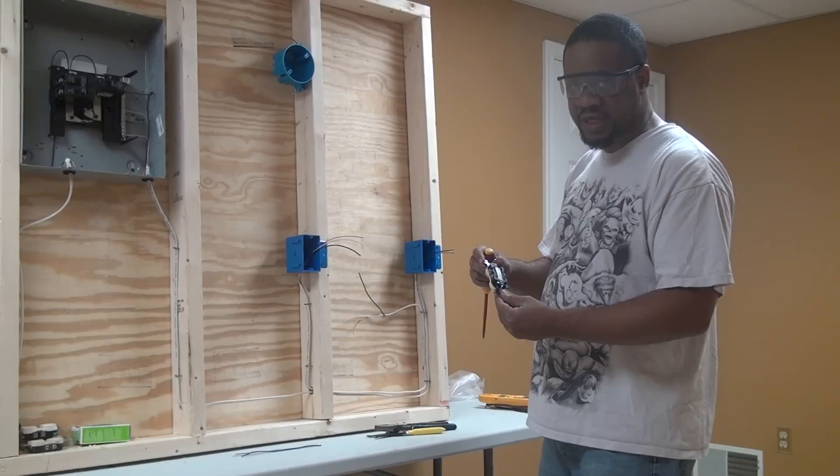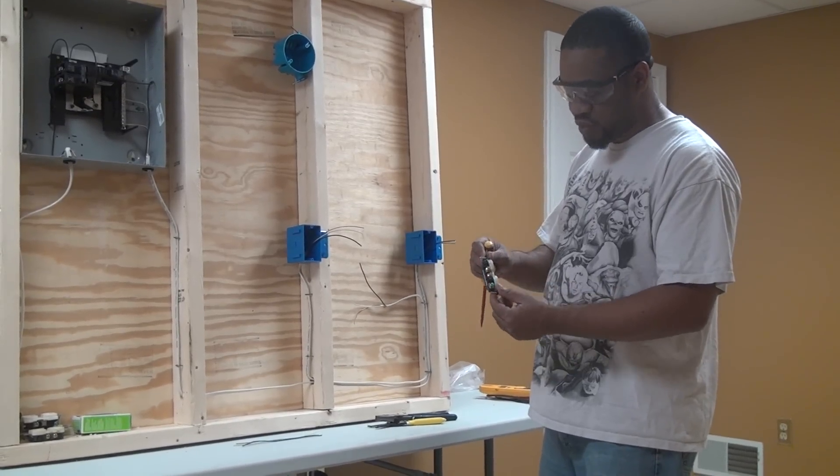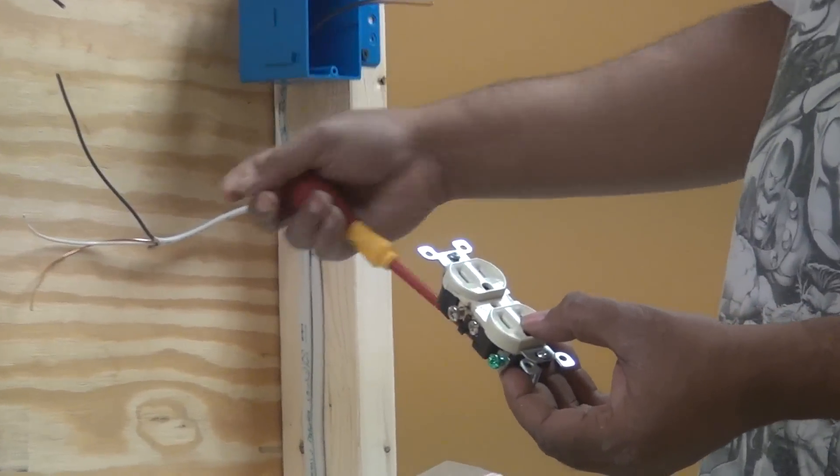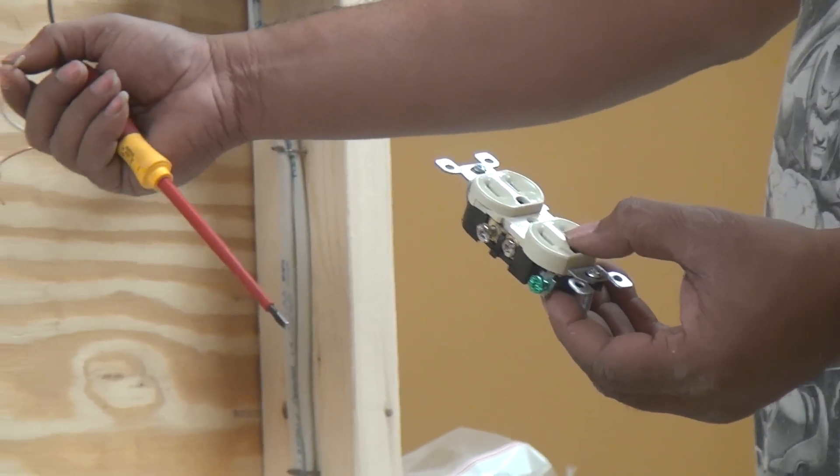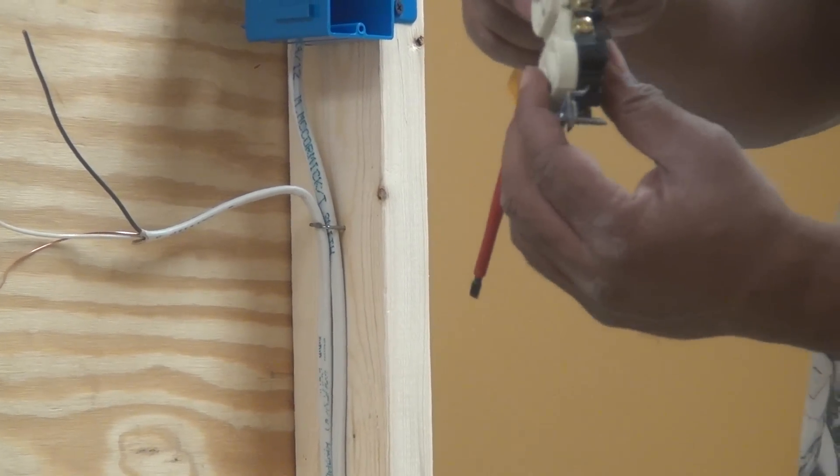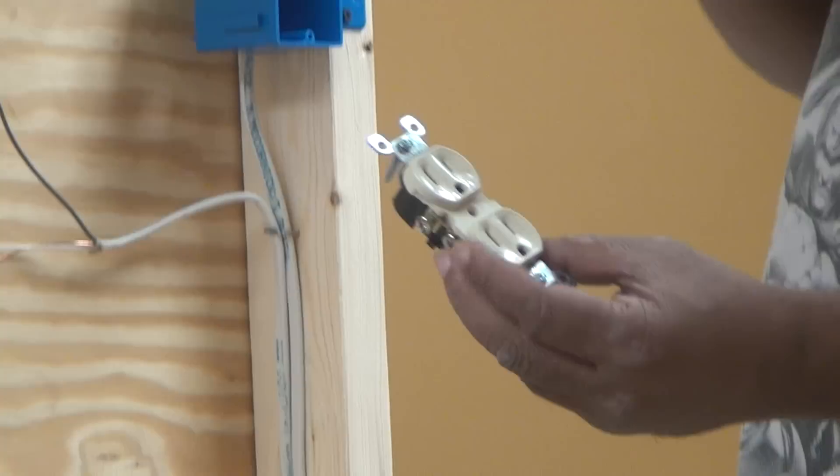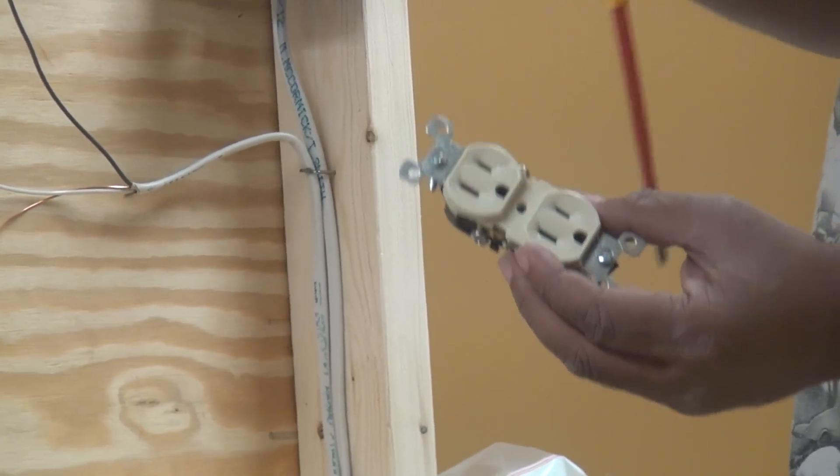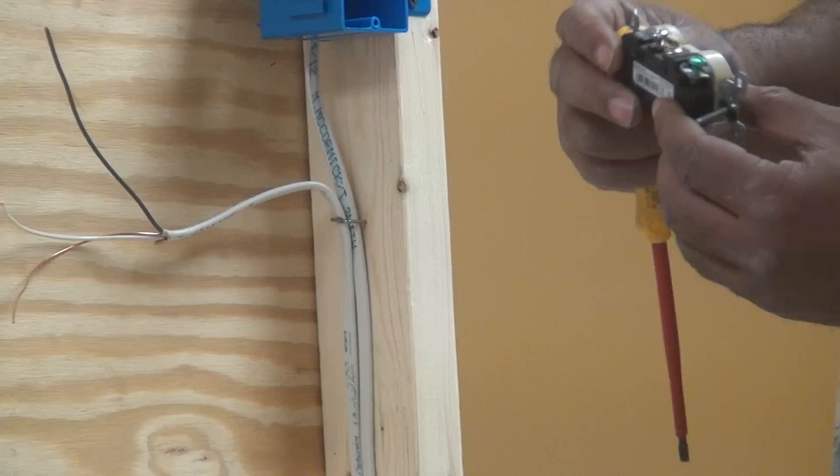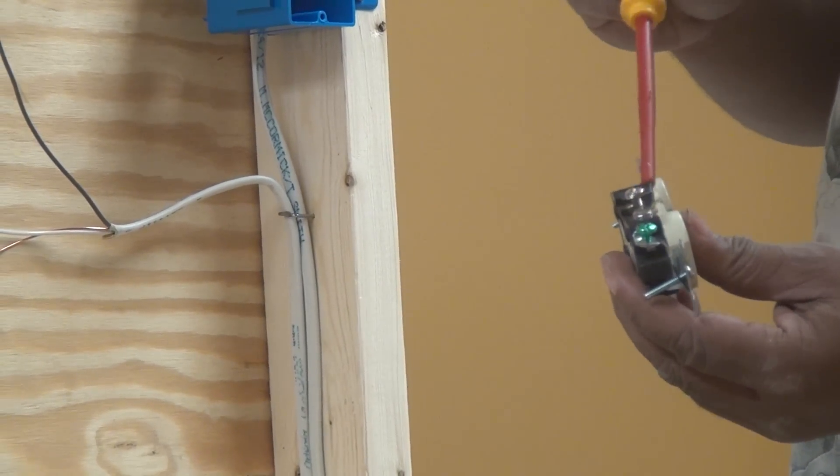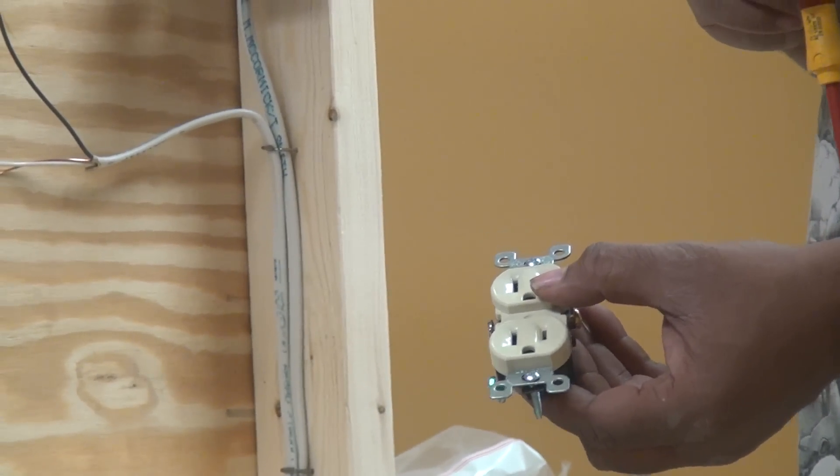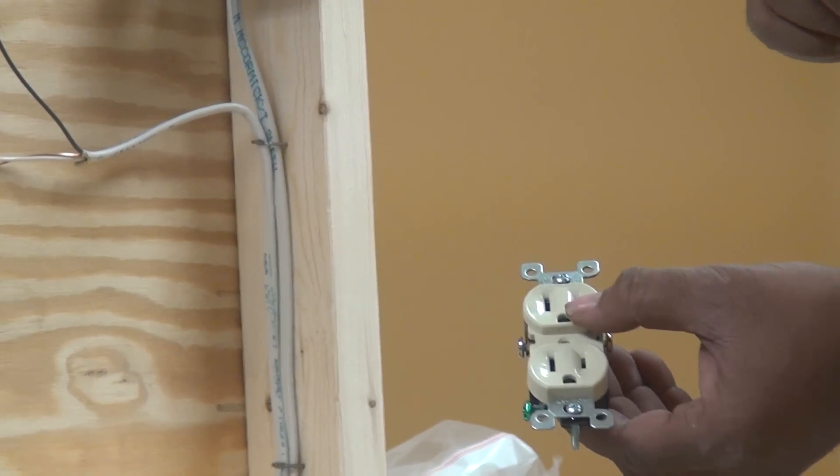the screws on the outlet are also colored. If you notice, one is silver, which connects to the neutral side, or that's where your white wire is going to go, the neutral or the grounded conductor. And the other side is bronze, or goldish-looking color. That's connected to the short side of the receptacle, or the ungrounded conductor, or the hot wire. That's where your black wire is going to go. And the green screw is connected to the little circular part here, which is your ground, or your equipment ground, or your grounding conductor.